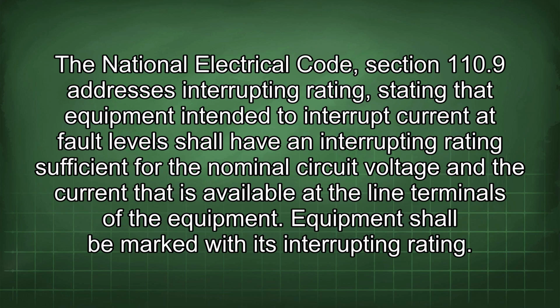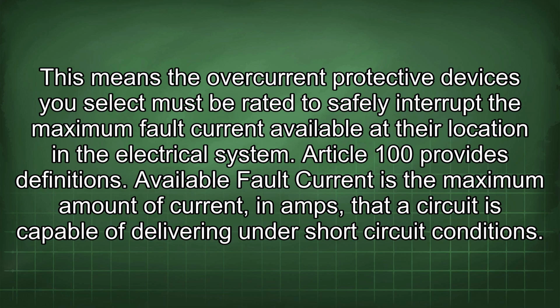The National Electrical Code, Section 110.9, addresses interrupting rating, stating that equipment intended to interrupt current at fault levels shall have an interrupting rating sufficient for the nominal circuit voltage and the current that is available at the line terminals of the equipment. Equipment shall be marked with its interrupting rating. This means the overcurrent protective devices you select must be rated to safely interrupt the maximum fault current available at their location in the electrical system.